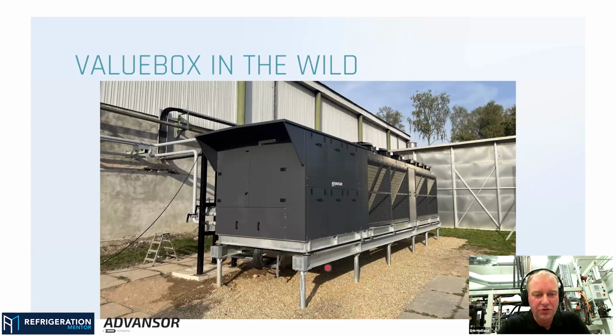Okay. Yeah, the contractor makes this platform here for the unit to stand on. It can be a bit hard to see, but we've got some machine shoes here, and there you have our skid on the top. So he makes this platform, and this platform is quite important because you need some space underneath the unit to draw in all the air. And also now in Latvia you get a bit of snow, so in the winter time all of this would be filled up with snow.